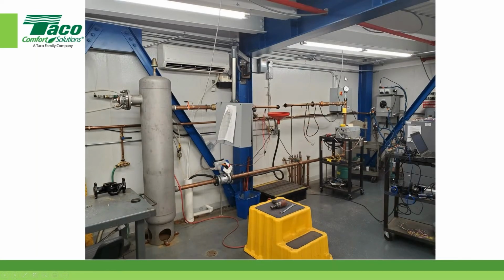Now this is just one of the little test benches in our lab. You know, we have the ability to test pumps as big as having a requirement of 20,000 gallons, right? So, I mean, we have two big buffer tanks. This is a little buffer tank, right? You can stand right up next to that. That's probably about maybe 5 or 6 foot tall. But imagine two 10,000 gallon buffer tanks that we use for some of our big pumps that we have to do sizing and flow verification on. So this is just a little test bench. You can see that they pulled the circulator out, and you can see this little catch basin and everything.